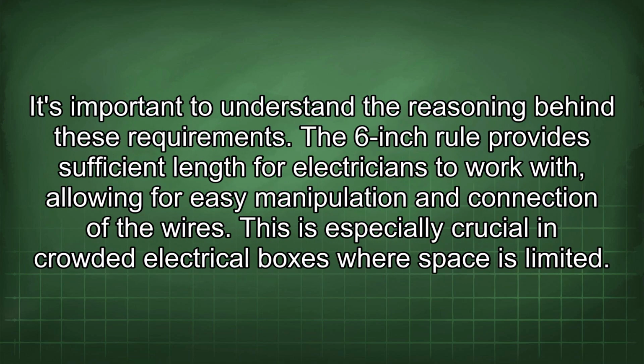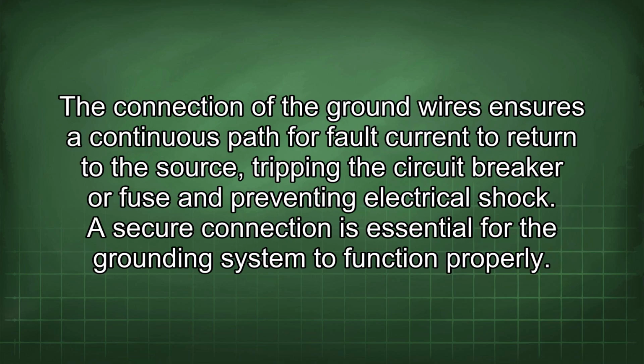It's important to understand the reasoning behind these requirements. The 6-inch rule provides sufficient length for electricians to work with, allowing for easy manipulation and connection of the wires. This is especially crucial in crowded electrical boxes where space is limited. The connection of the ground wires ensures a continuous path for fault current to return to the source, tripping the circuit breaker or fuse and preventing electrical shock. A secure connection is essential for the grounding system to function properly.